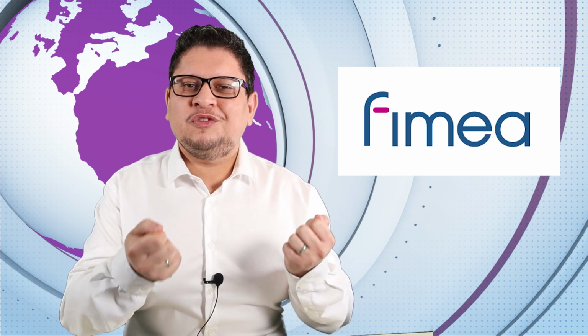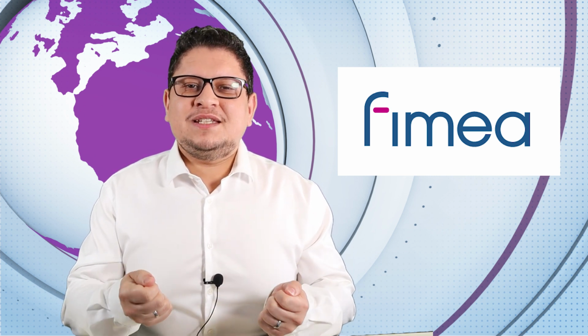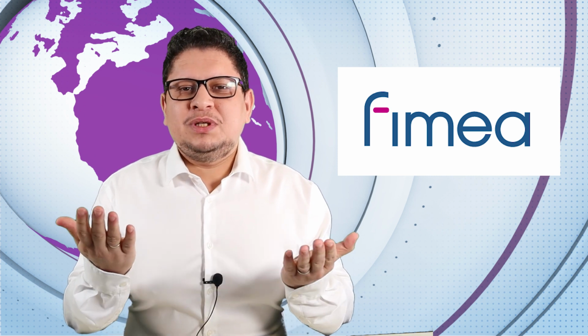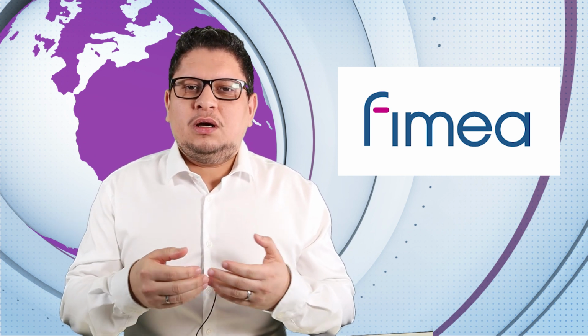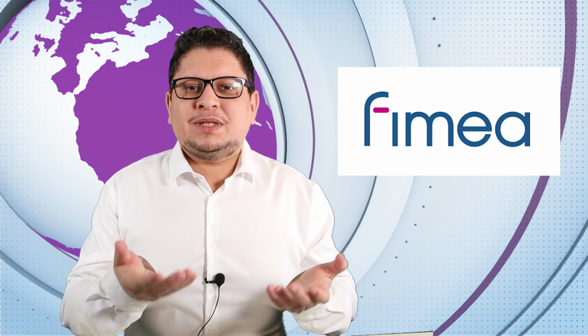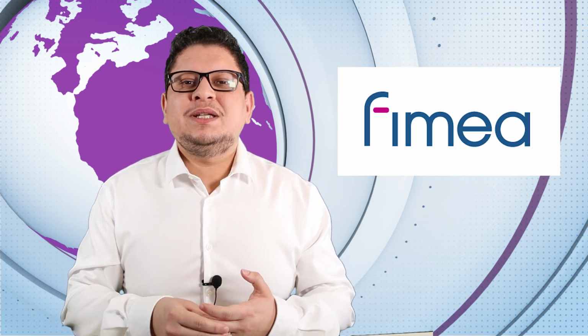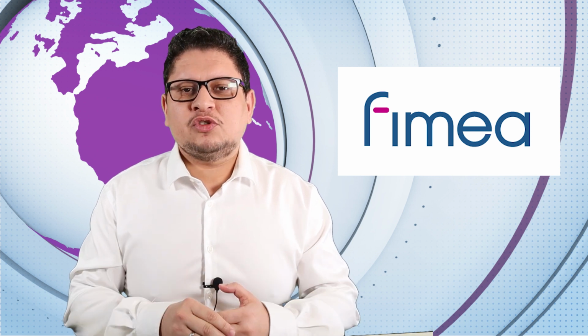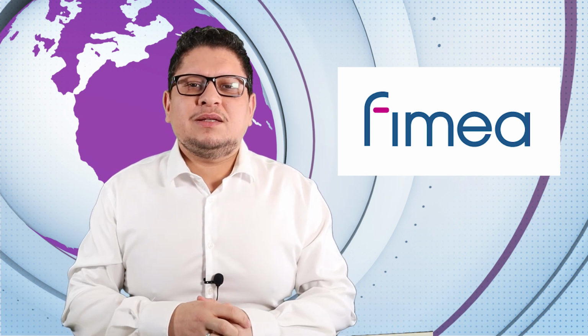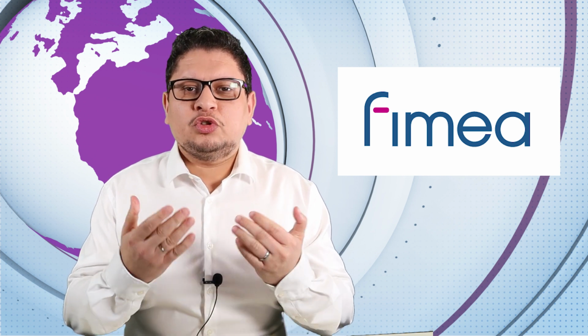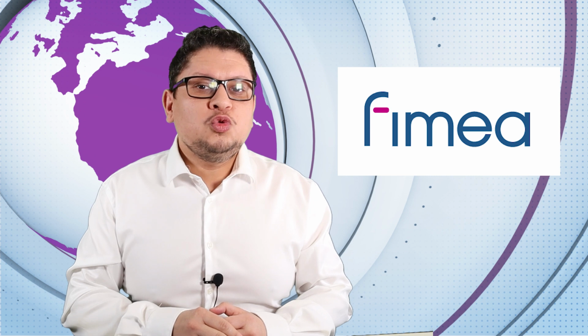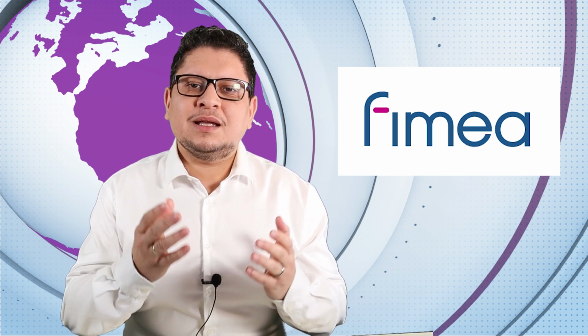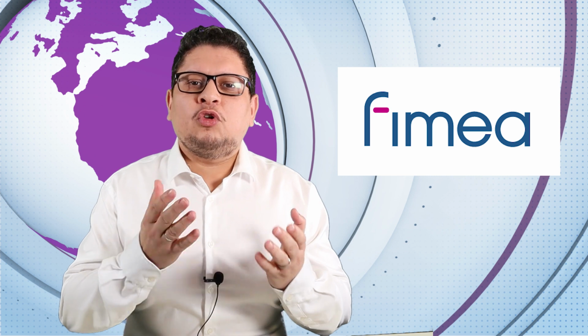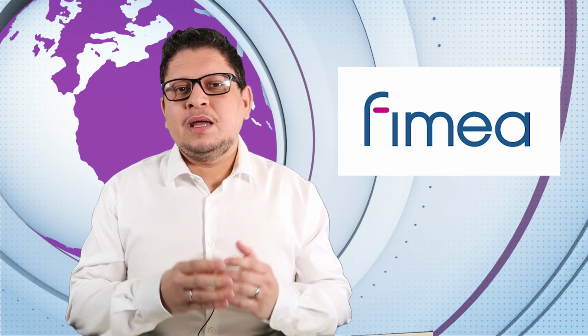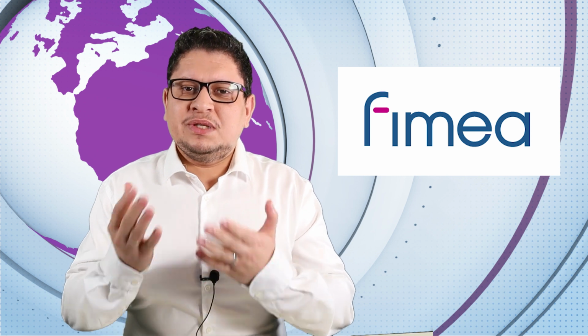I read the IFU of one that was for self-testing and one that was more for professionals, and you can really see the difference, because one is made more understandable by a professional that knows what he's doing, and one really tries to make it easier for laypersons, so that are you and me. So you really have to be careful if you are an importer or distributor, but also if you are a user of those devices, to have a clear understanding that these are targeted for professionals when there is just a CE mark, and these are targeted for laypersons when there is a CE plus the number, the notified body number.